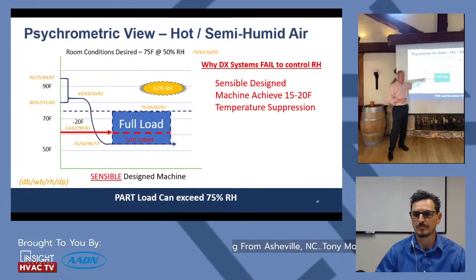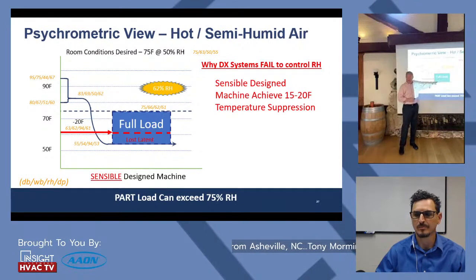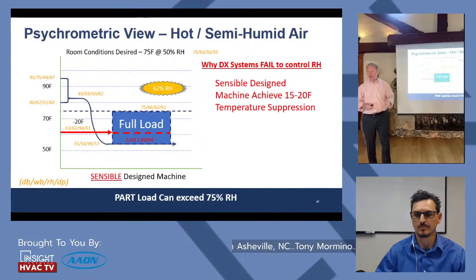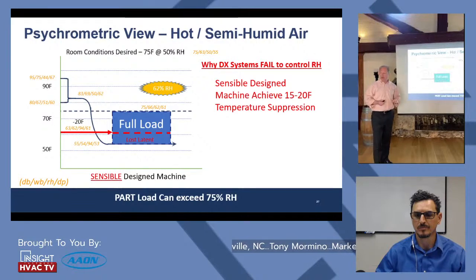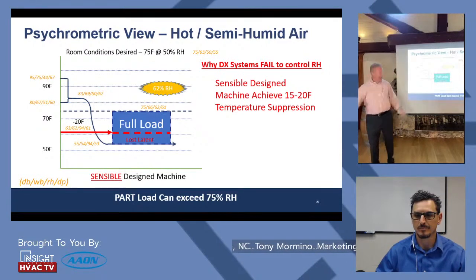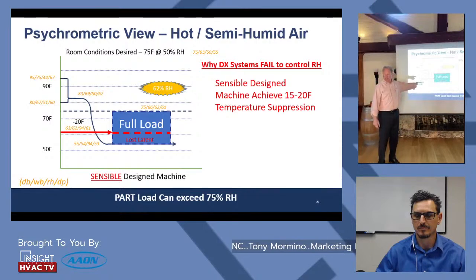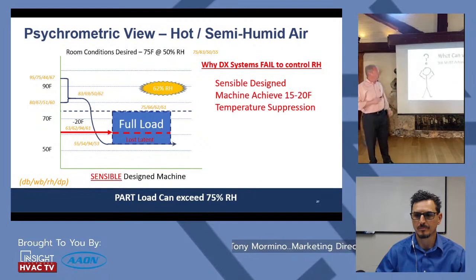A sensible design machine with a 20°F temperature suppression holding 94% RH leaving the coil ends up at a 61°F dew point — we've lost latent control. That machine wasn't equipped to handle all of that moisture removal. Many contractors have heard owners say 'I can't afford that machine, just put this one in' — and then they come back complaining they can't control humidity. That's exactly what we're dealing with.